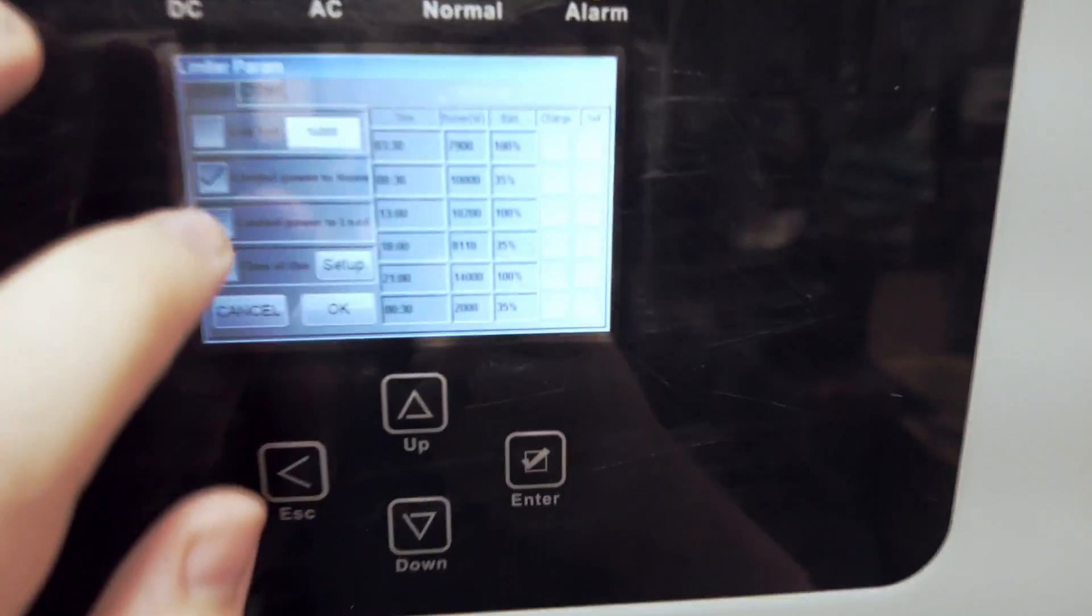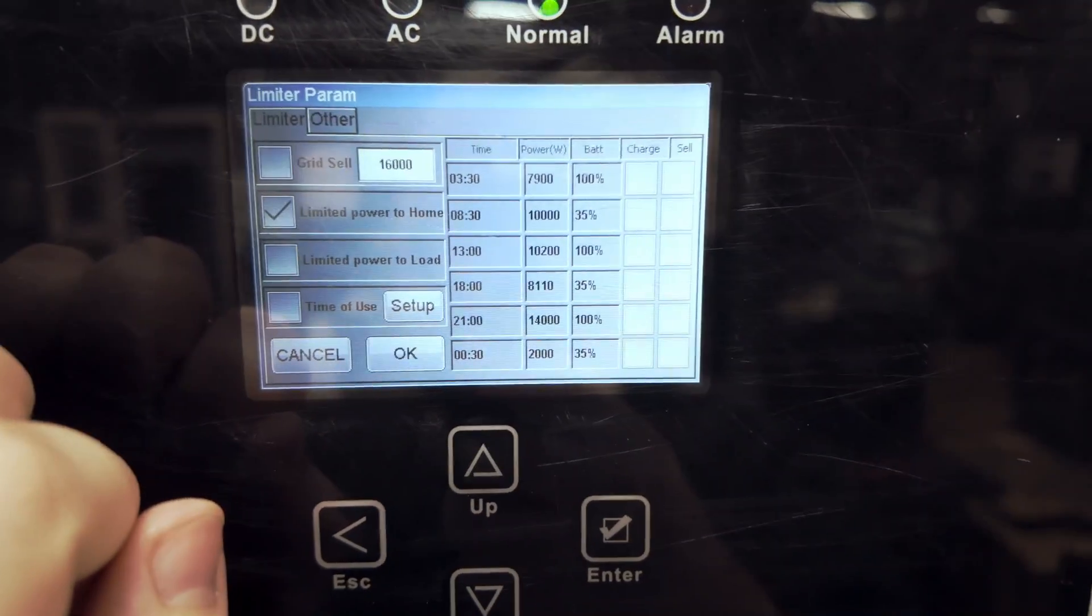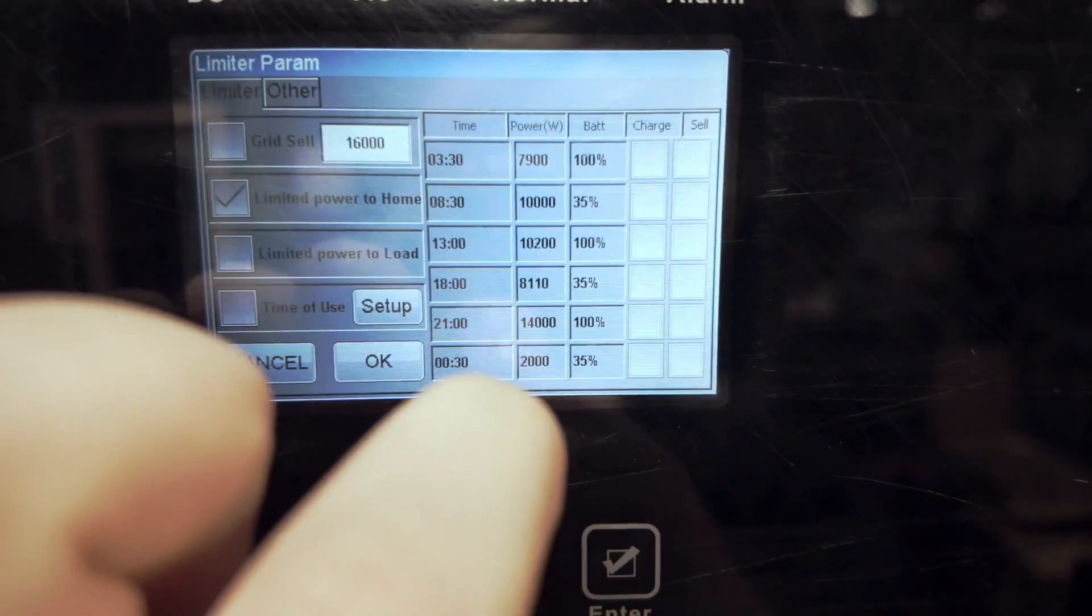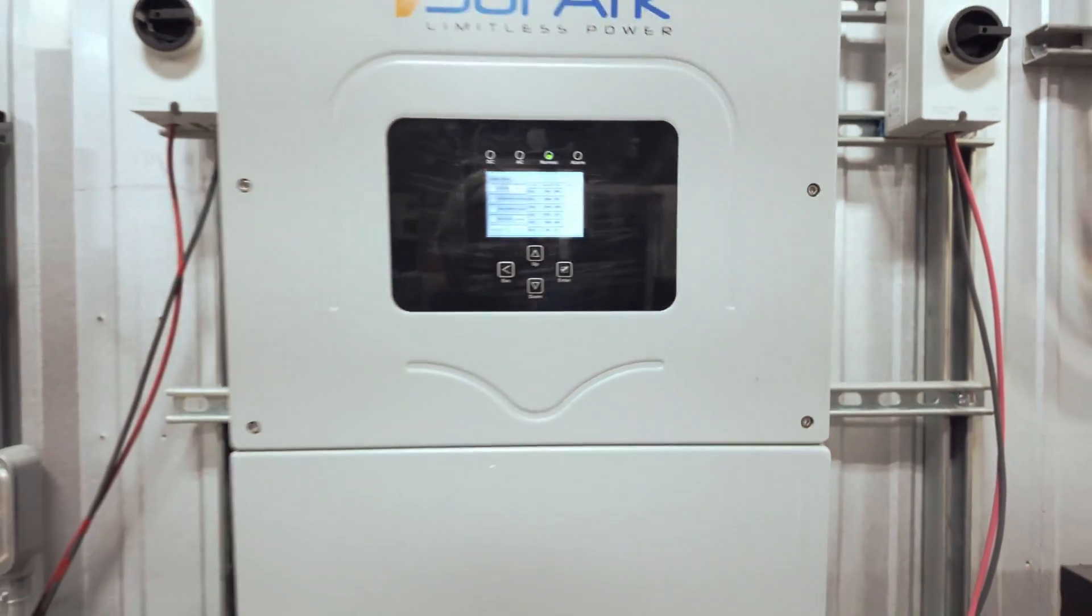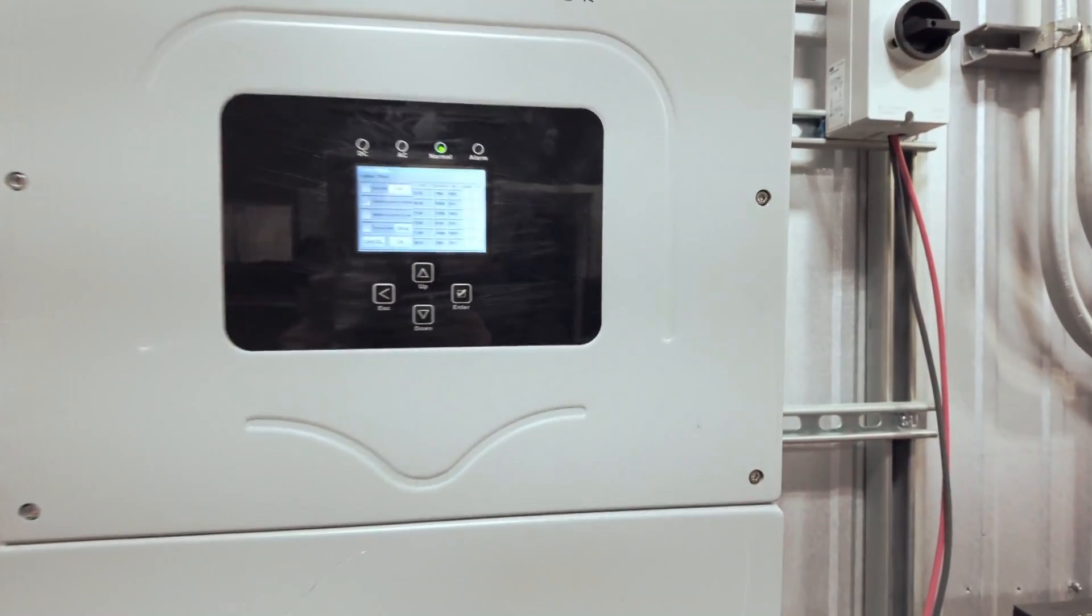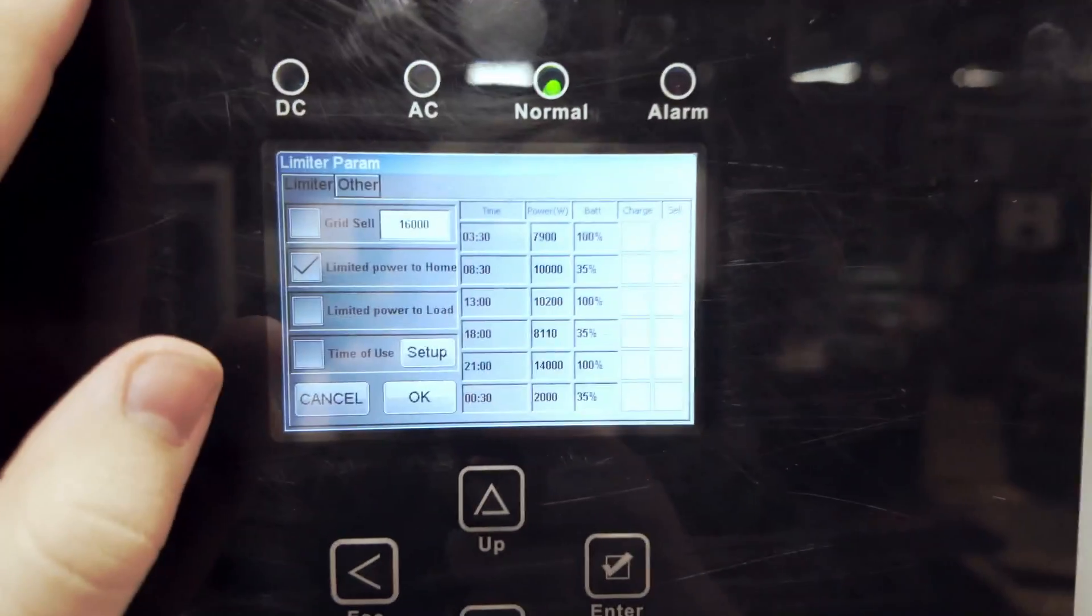Now, this just is the way that the time of use works on the Solark. If you're very familiar with the settings that you have here, you'll only be able to operate it within those parameters. So if you aren't super familiar with the way that works, you don't want to use time of use when you're initially testing it to make sure everything is working properly.